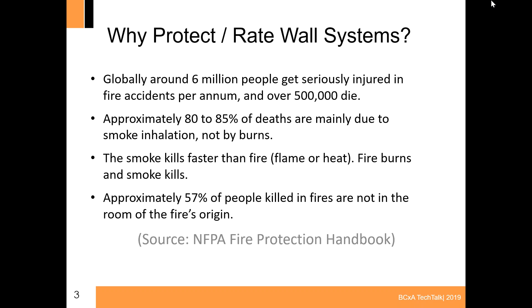So how fast does smoke travel? As a simple example, unfortunately we don't have a video to show, but a simple 10 millimeter hole can have smoke traveling through it anywhere from 120 to 420 feet per minute, bringing smoke into a safe area. So we need to truly make sure these gaps and holes, whether vertical or horizontal, are closed so we can keep smoke inside the smoke barrier where the condition is occurring.